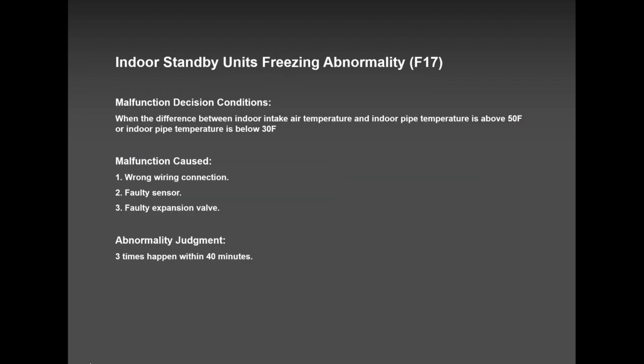F17. F17 is coming up now. The contractor says, Paul, it ran the whole winter, no problem. I said, yes, it ran the whole winter because there is no error code of cross wiring in heat mode. The error code will pop out only in cool mode. And that's where you get the F17 or the H39.